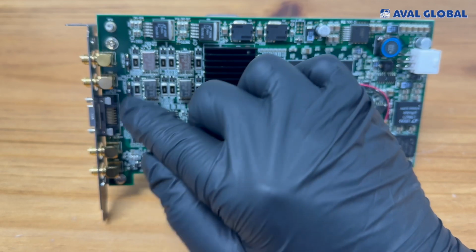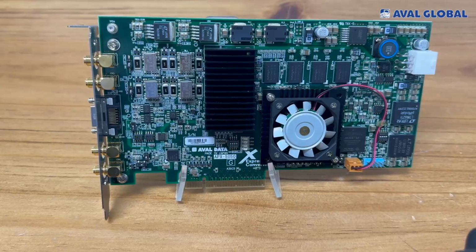Switch 6, switch 7 are located at the top right of the board, and when turned on, they set the calibration for each channel. The initial value is off, and this switch is only used when performing calibration or product calibration using a reference voltage. Please do not use it in general.